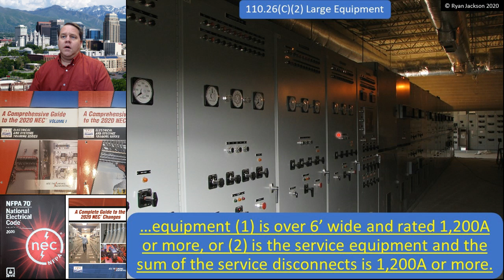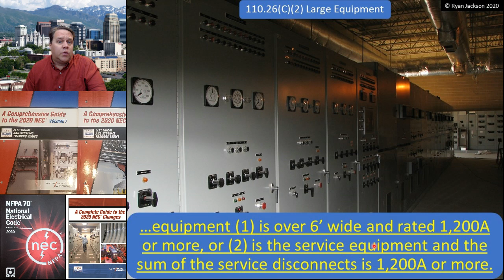Another example here. Here's my long switchgear. It's pretty obvious that I have an exit at the end down here, so I'm good. I would need another exit on the close end of the photograph unless I met the exceptions, and it looks like this probably does meet the exceptions, and we're not going to get into those. The other thing, though, is that now this rule comes into play if the equipment is the service disconnect, the service equipment, and the sum of the service disconnects is 1200 amps or more. All right, so I have my 2 independent pieces of switchboard. If those combined equal 1200 amps and it's 6 feet or more, then I would have to comply with this section.